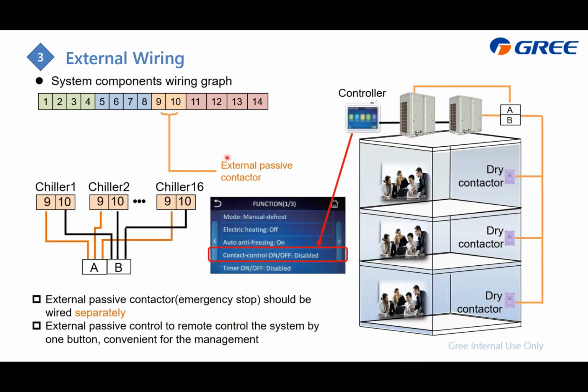As for the external passive control, which is just like this one, in this case you can find that we install this chiller system, and you can have this button to connect to this A and B, which then connects to the chillers. At the controller, don't forget to enable it. The detail wiring is to this 9 and 10. You should also make it separate for different chillers.